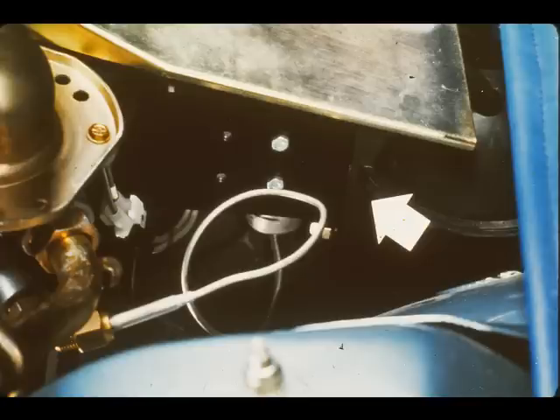The high pressure or Ranco switch, arrowed, senses the pressure at the valves in receiver unit. Incidentally, the operation of this unit is described in the product training workbook on the ROVER air conditioning system. If the pressure reaches a critical level, the switch closes, energizing the cooling fan relay. The cooling fans operate, increasing the airflow through the condenser.